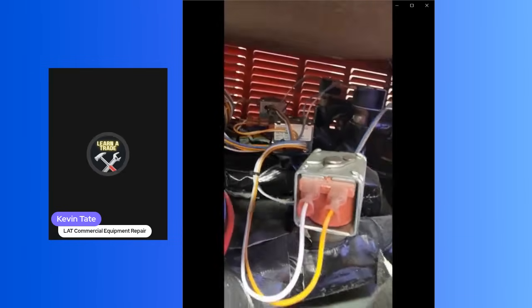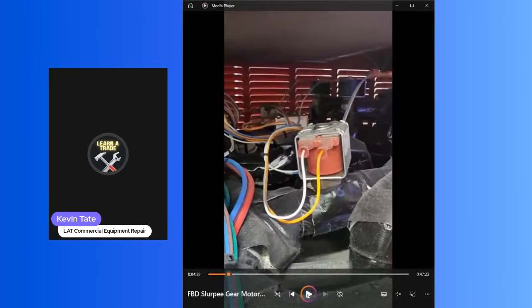Going up top, you're looking at the hot gas valves right here. If you can see the cursor moving around, those are your hot gas valves - you've got three of those. Just above those you have three pulse valves. Your pulse valves, when it's freezing down, that's what you're hearing when you hear that clicking sound - those are your pulse valves letting refrigerant through.